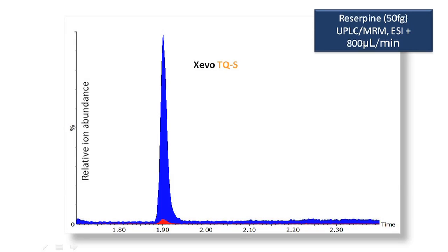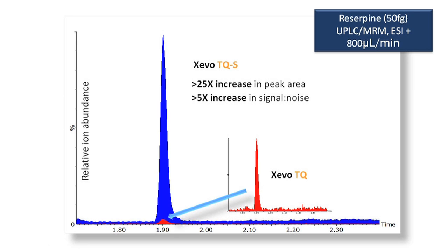The StepWave ion guide provides up to 25 times more ion current than the standard single ion guide. This is achieved whilst providing a system which is significantly more robust than previous designs, allowing customers to run many thousands of samples at the highest levels of performance.